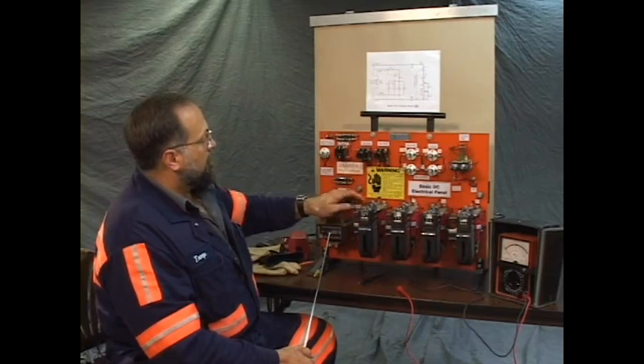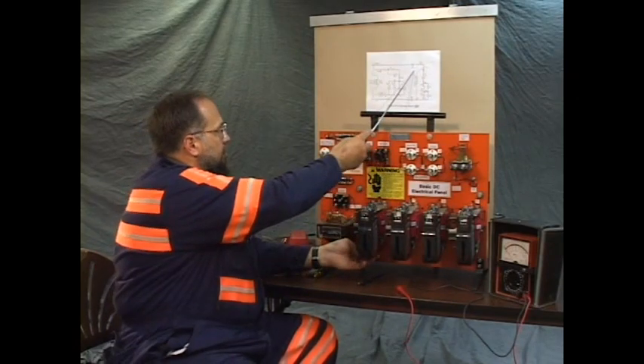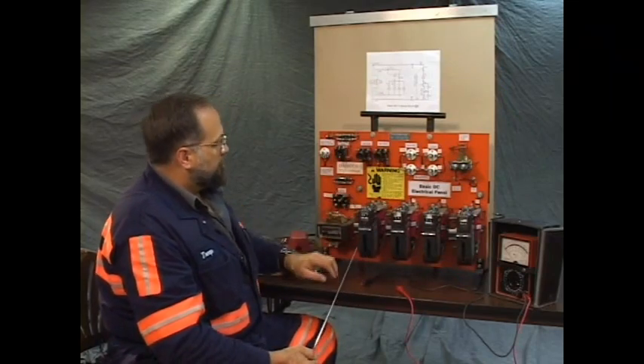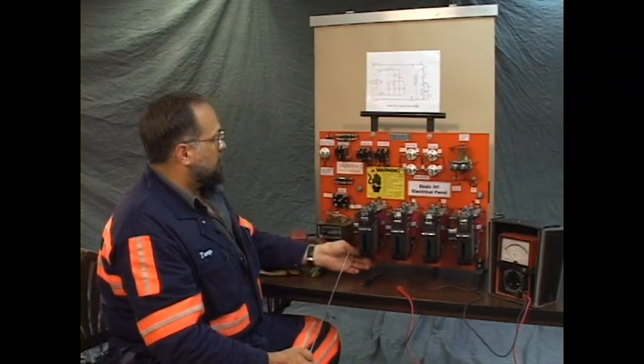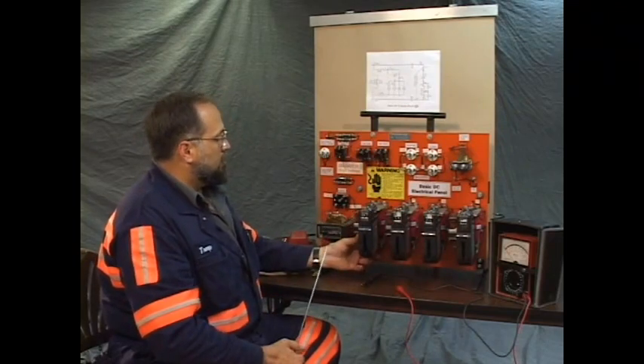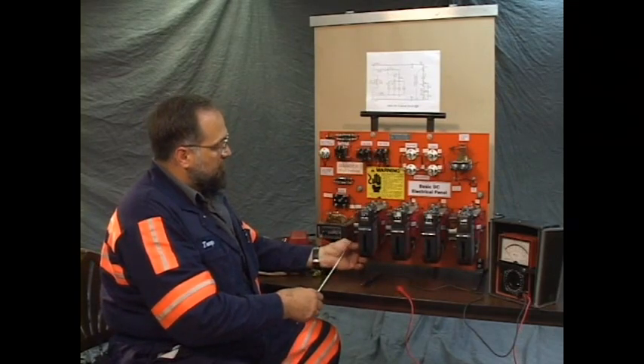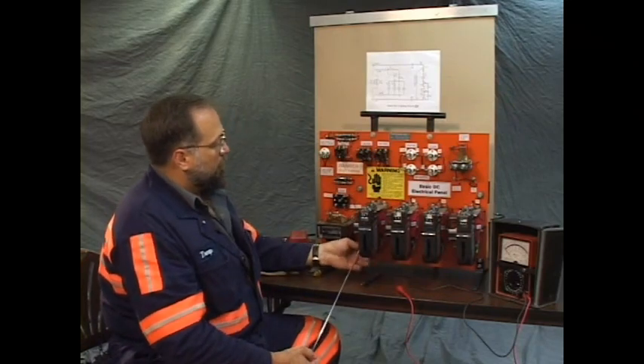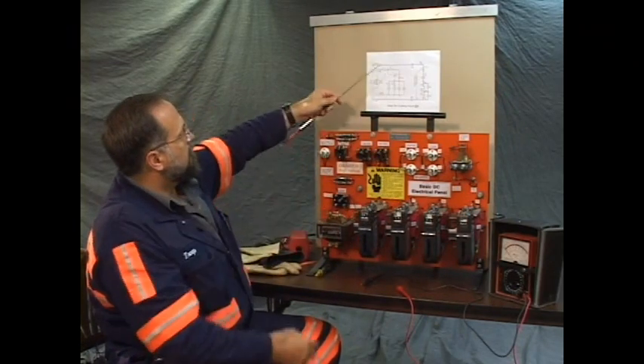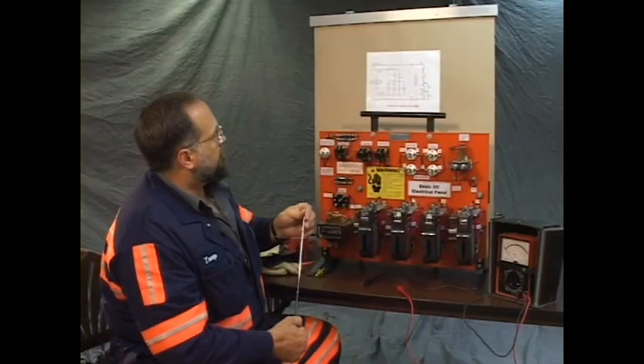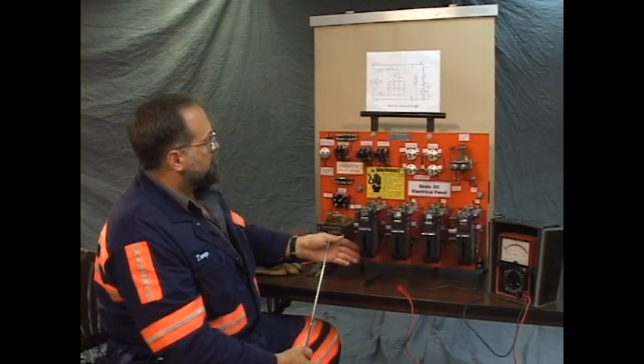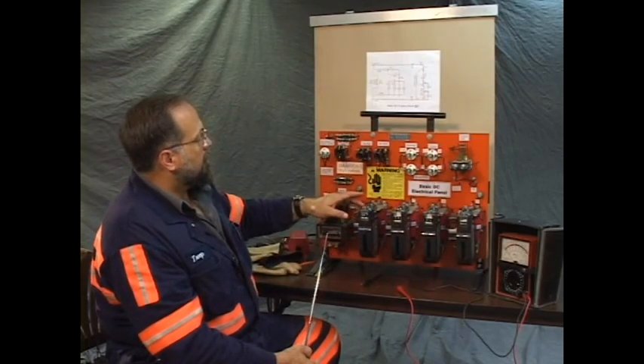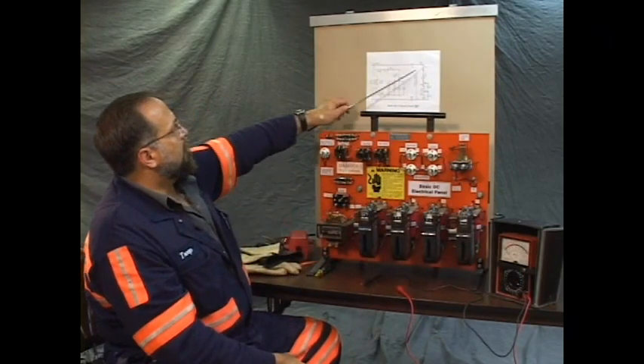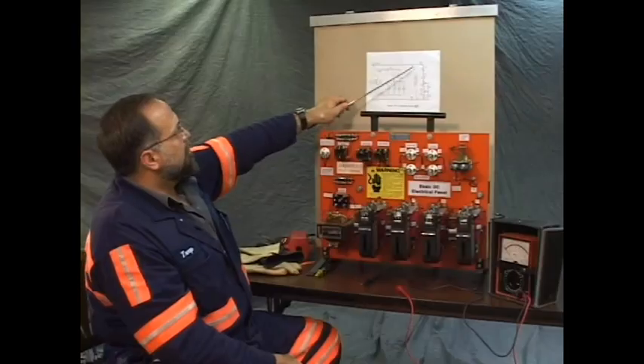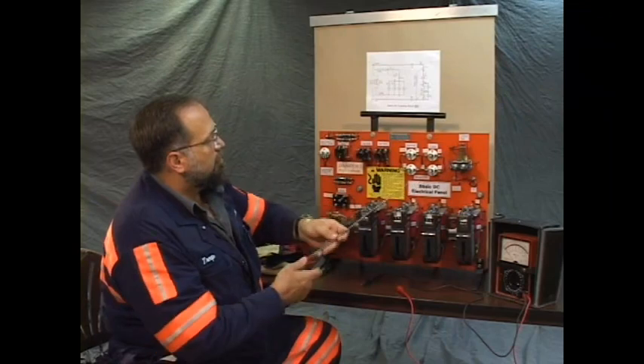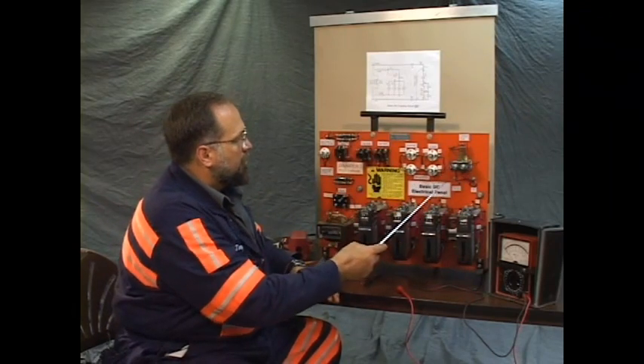When you energize the coil, it makes a magnet to pull the contact tips together. And the M1 mercury tube, it's an auxiliary device, also operated by the coil. When the coil pulls in, there's a little arm that transfers magnetism from the coil to pull mercury and make these contacts right here. Everything labeled M1 is controlled by the M1 contactor, by the M1 coil. You have the OL1. We have an OL1 mercury tube. This is the coil for OL1. It's the bottom portion of this, the heavy wiring, the power wiring.